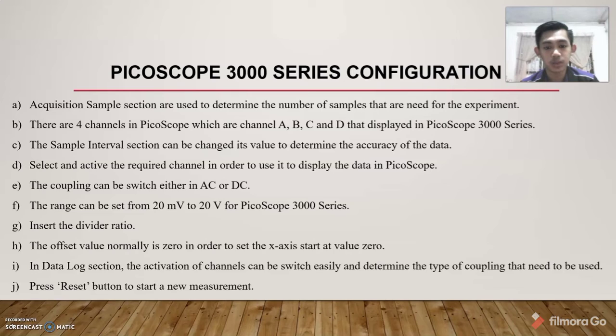The coupling can be either AC or DC. Set the coupling AC for channel A and coupling DC for channel B. The range can be set from 20 mV to 20 V for picoscope 3000 series. The important section in picoscope 3000 series is the divider ratio. So we need to insert the divider ratio value of 19651.1 because the divider ratio of secondary capacitor AC that is being used in the experiment is 19651.1 in channel A.